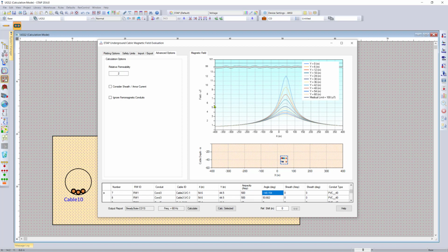The tool therefore allows you to evaluate three magnetic field exposure limits, which are worker, general public, and individuals with medical condition. The biggest value of this tool is to determine if personnel sensitive to the potentially harmful effects of magnetic field exposure, such as individuals with pacemakers, are not being exposed to long-term magnetic fields above the recommended limits.